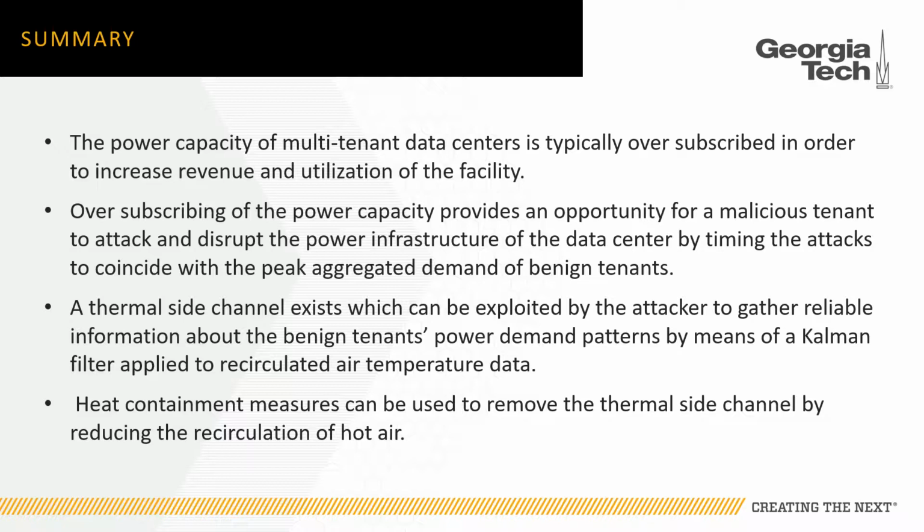In the paper, a thermal side channel has been identified, which can be exploited by the attacker to gather reliable information about the benign tenants' power demand patterns by means of a Kalman filter applied to recirculated air temperature data. And the paper finally provides a series of countermeasures that can be used to mitigate or prevent this type of attack.